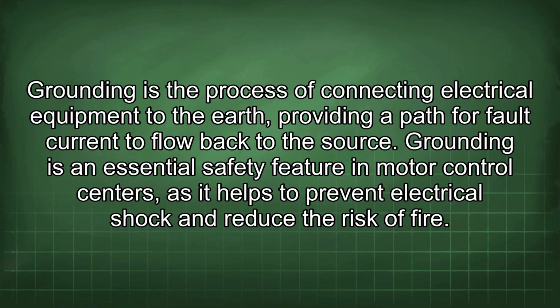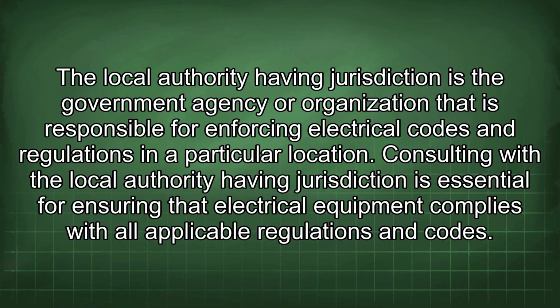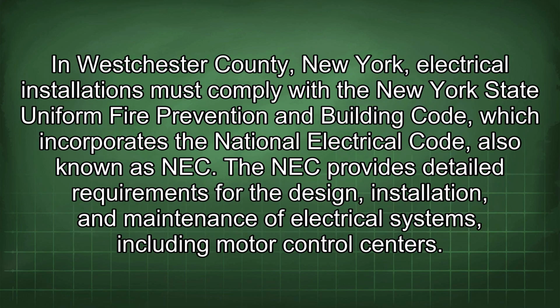Grounding is the process of connecting electrical equipment to the earth, providing a path for fault current to flow back to the source. Grounding is an essential safety feature in motor control centers, as it helps to prevent electrical shock and reduce the risk of fire. The local authority having jurisdiction is the government agency or organization that is responsible for enforcing electrical codes and regulations in a particular location. Consulting with the local authority having jurisdiction is essential for ensuring that electrical equipment complies with all applicable regulations and codes. In Westchester County, New York, electrical installations must comply with the New York State Uniform Fire Prevention and Building Code, which incorporates the National Electrical Code, also known as NEC. The NEC provides detailed requirements for the design, installation, and maintenance of electrical systems, including motor control centers.